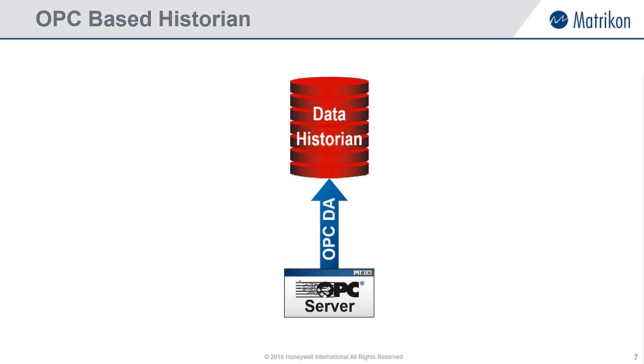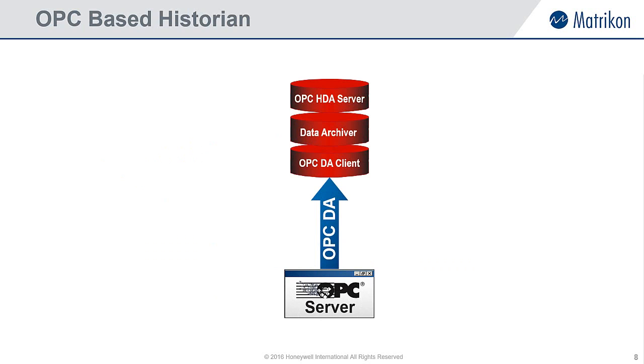So how does it work? Let's take a closer look at an OPC-based data historian. The OPC-based data historian contains three key components. Firstly, an OPC-DA client, which enables the historian to connect to OPC-DA servers in order to collect real-time data. The next piece is the archiver or core component, responsible for taking the collected data and storing it to disk. And lastly, an OPC-HDA server, which allows external OPC-HDA enabled tools to connect to the data archive and access the stored data.